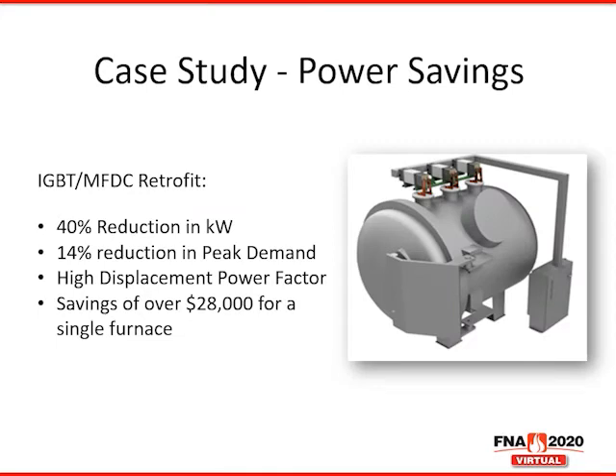In this presentation, we're going to go over a case study for an IGBT MFDC retrofit of a VRT furnace. In this case study, we will demonstrate a 40% reduction in kilowatts, a 14% reduction in peak demand, high displacement power factor, which correlates to lower costs, and a savings of over $28,000 for a single furnace.